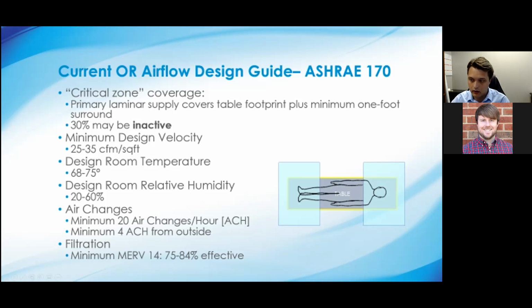And that gets more evident when you skip down to the bottom here. If you look at the filtration requirements, minimum filtration was MERV 14, which only stops 75 to 84% of particles from reaching that patient. So there's no way that you can actually predict how clean the air is going to be in that room by designing to ASHRAE 170, because the cleanliness of that air is totally dependent on how clean the air you're filtering is to begin with. You're not filtering it with HEPA filtration all the time, and so you could still be delivering contaminated air directly over that patient.